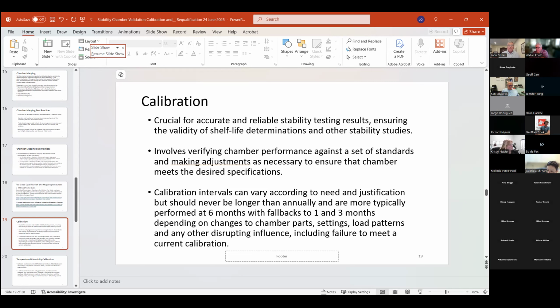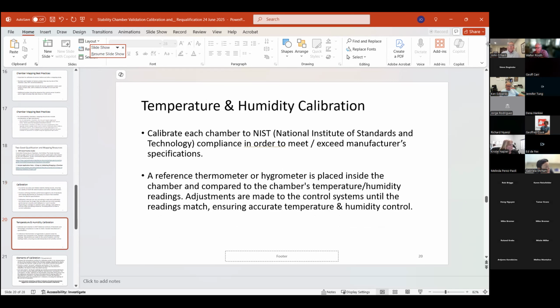And as soon as we had a failure or made a change, we would bump it back to 3 months or even 1 if necessary to show that was going on. We have to have a bunch of material here on calibration. For temperature and humidity, calibrate each chamber to the National Institute of Standards and Technology specifications in order to meet their manufacturer specs as well.